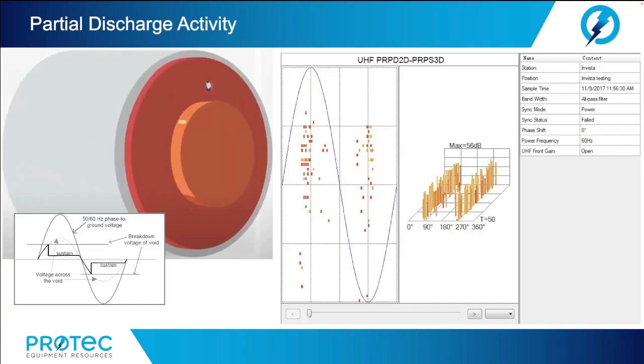As the insulation deteriorates, the partial discharges will begin earlier and they will extinguish later as its ability to withstand the voltage stresses diminishes. Meanwhile, all the other noise and other signals in the detection bandwidth of the sensor will arrive at random time intervals that are not equal to 8.3 milliseconds. Noise arrives at random points along the x-axis, whereas partial discharge pulses arrive at 180-degree intervals.